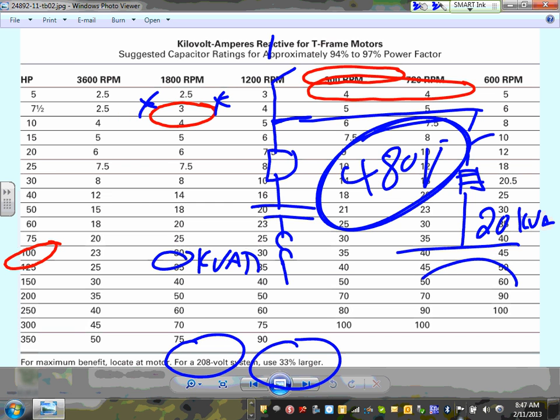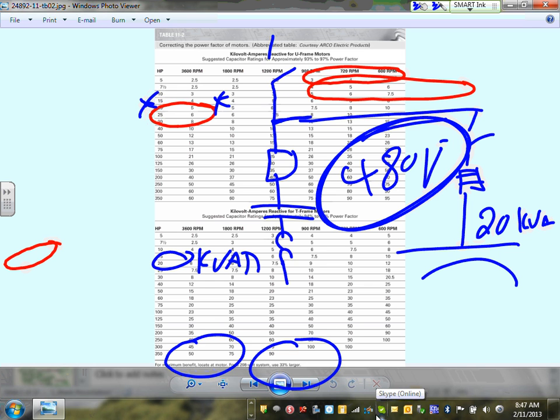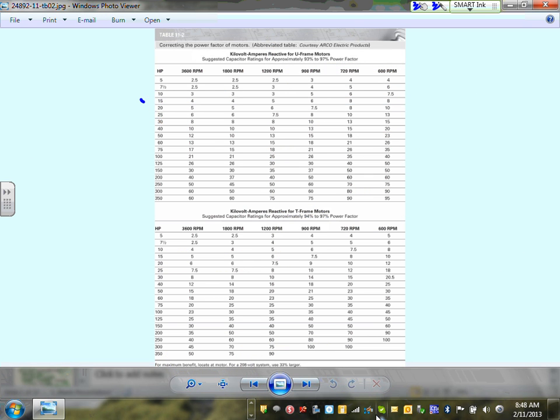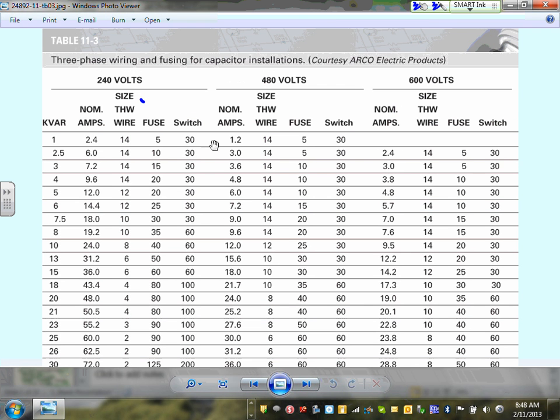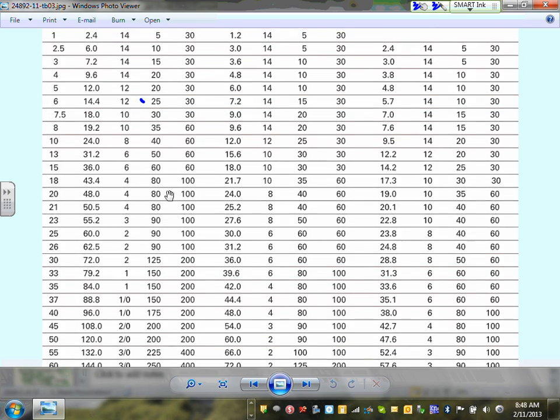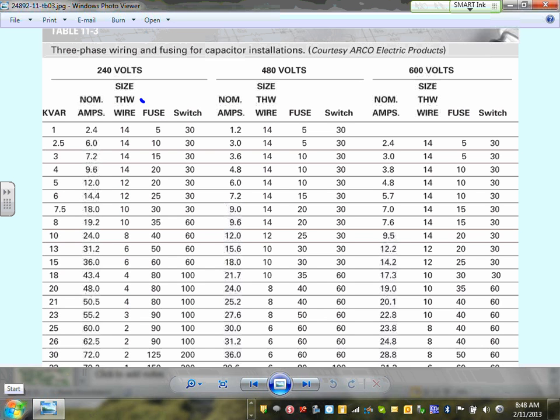Any comments, any questions about this table? So that's how you correct the rich man's way, meaning you will have multiple capacitors right by the offenders. The last thing I'm going to do, and I promise this time it will be the last thing, is, they have a table in your book that actually tells you the sizing right from the get-go. Take this, Jeff. Where's the 20? Look at the 20. Here's my 20 kVAR that I sized. Here's the full load amp for it, calculated. Here's the THW wire size, number 4. And here's the fuse that you need. And here's the disconnect that you need.